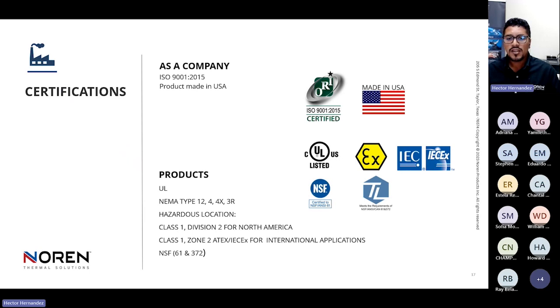Our products can be certified according to the environment where they are going to be operating. We have Type 12 for indoor use, which withstands dust and spray water. We have NEMA Type 4 for indoor and outdoor use, which withstands dust, water, rain, and snow. We have NEMA Type 4X, which withstands dust, water, snow, and moisture.